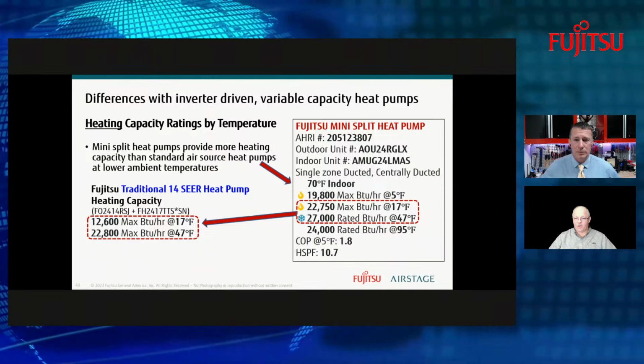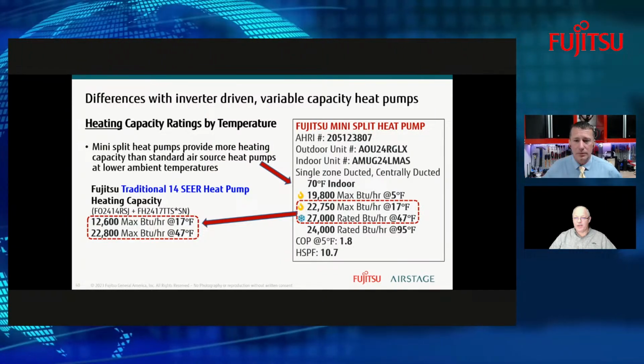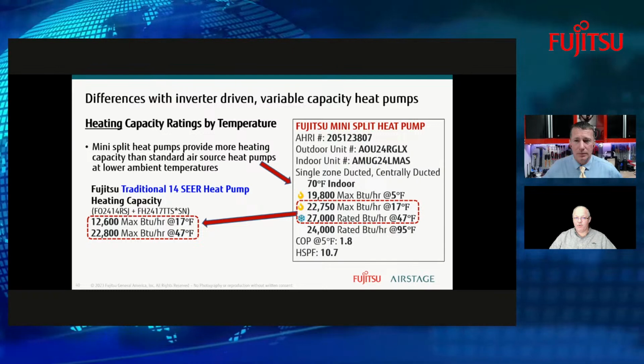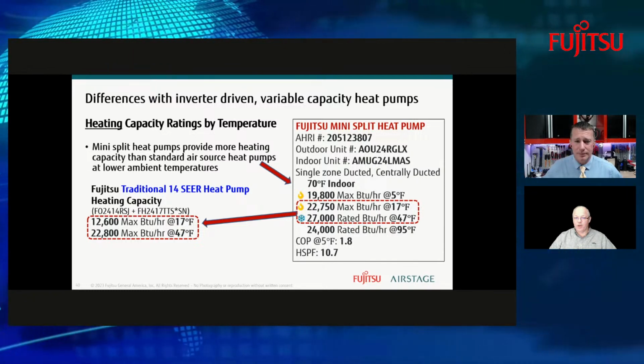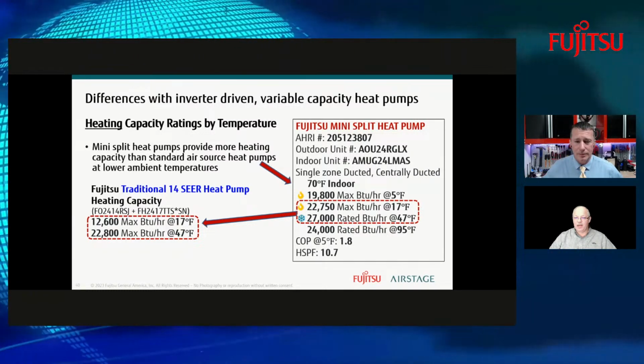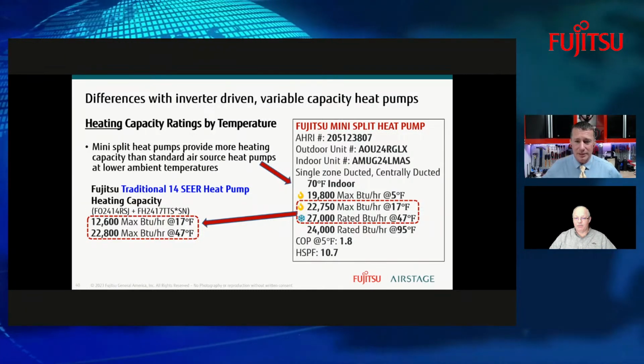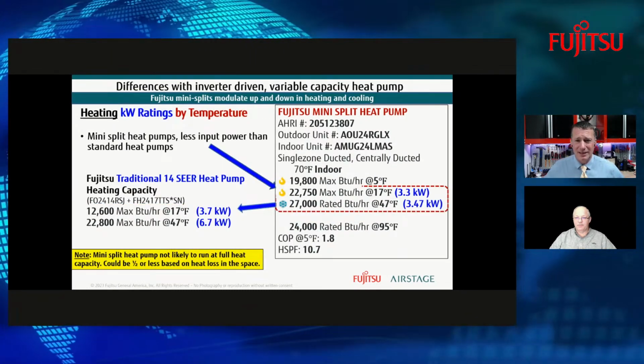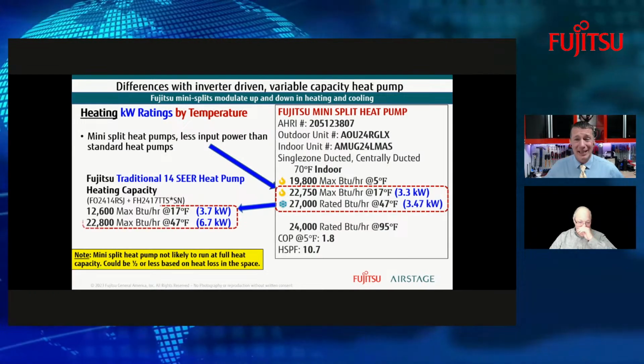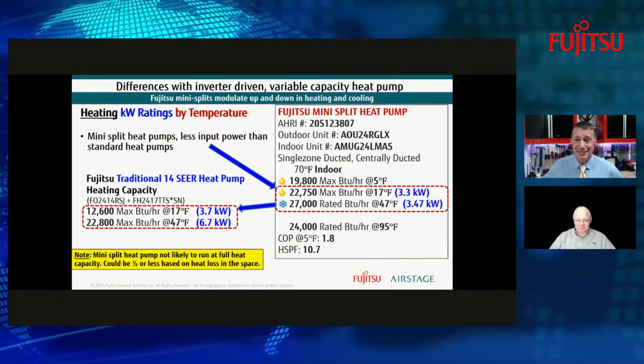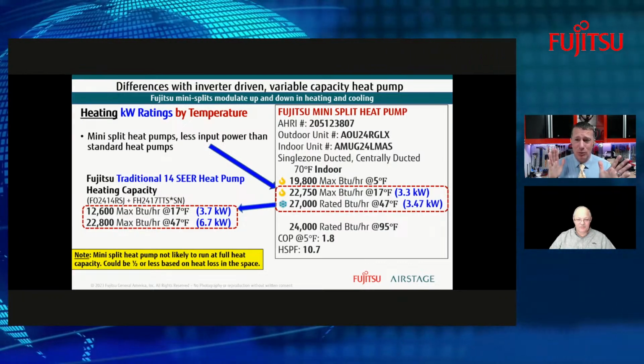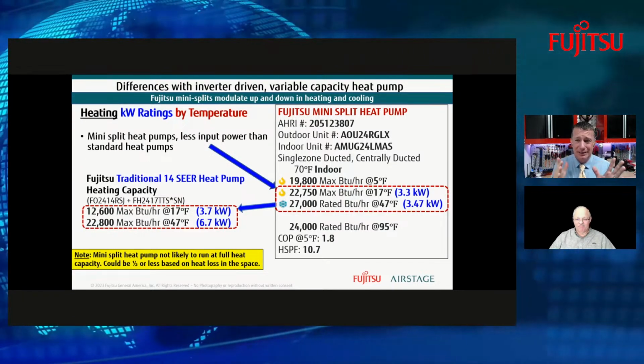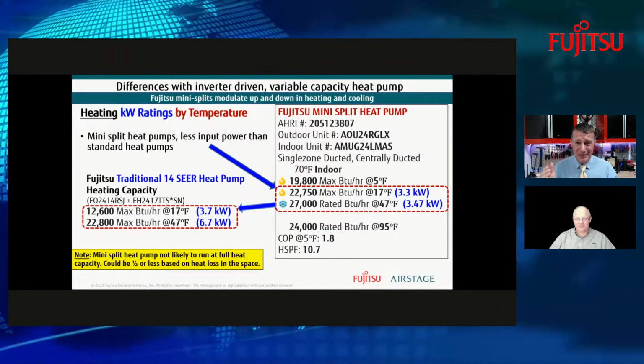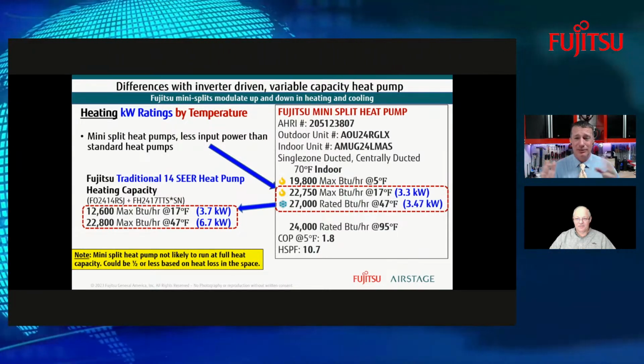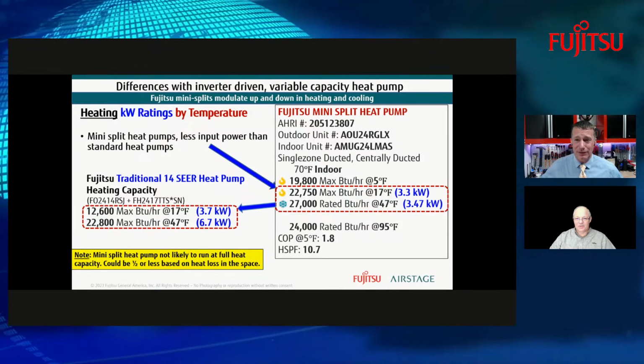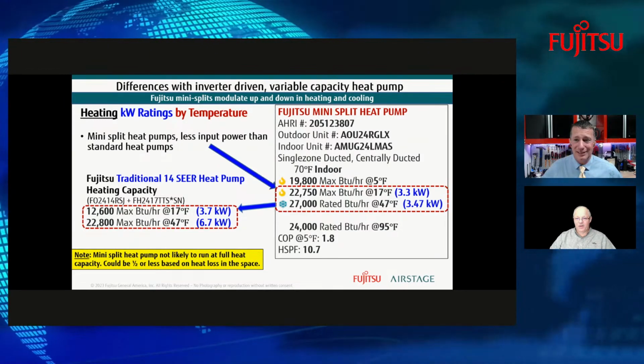You start getting into colder outdoor temperatures. That's what separates heat pumps on the mini split side from traditional. We can generate so much more heat that it's possible that we don't even need auxiliary heat backup. Especially when we look at the COP performance at 5 degrees, we're still 80% more efficient than an electric heat. Electric heat runs at a 1.0 COP, 1 watt in, 1 watt out. We're running 1.8 watts of heat output for every watt of electrical coming in. So significantly more efficient than electric resistance heating.